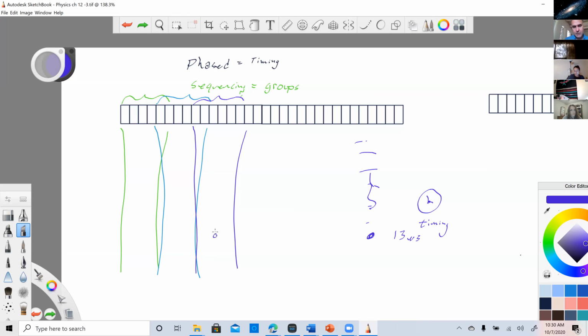If this object is seen at 13 microseconds timing, in other words, 1 centimeter away, we know it goes at 1 centimeter of depth on the screen, but the machine also knows that this particular beam found this particular object by listening to its echo. So now we know that not only is it 1 centimeter deep, but it's to the left of the screen, or to the right. It now knows where to put this echo laterally because it came from that particular beam.